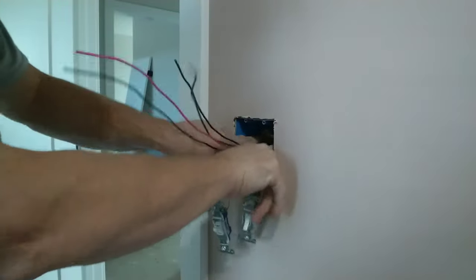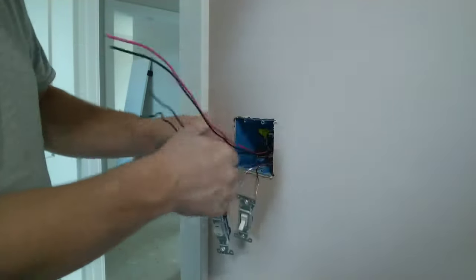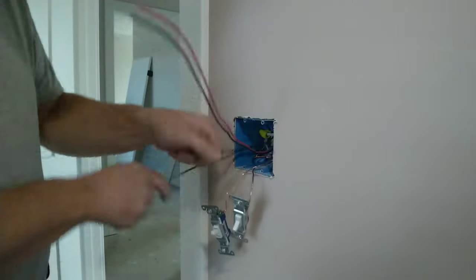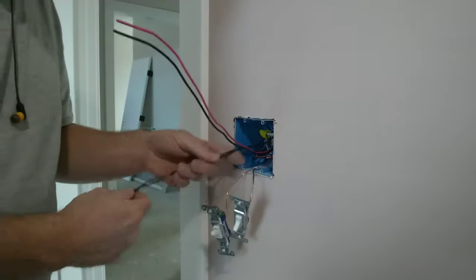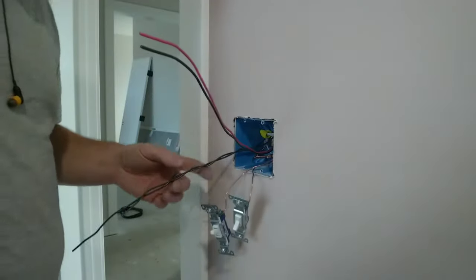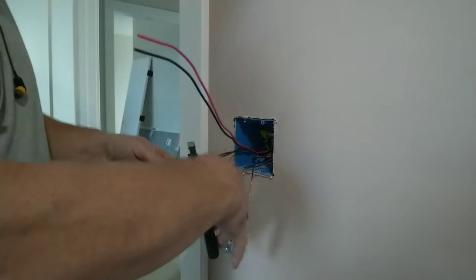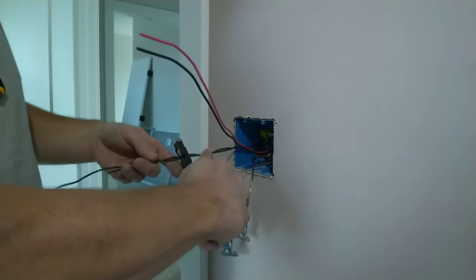So now that I got that snug, we're gonna take that neutral. We're gonna do a nice little coil to the back of the box. Now we're gonna do our hots, okay? We got a feed in, feed out. We're gonna spiral these together. And on doing this job, we need two pigtails. So what I'm gonna do, gotta do a minimum of 6 inches from the back of the box. I'm gonna cut it, okay?